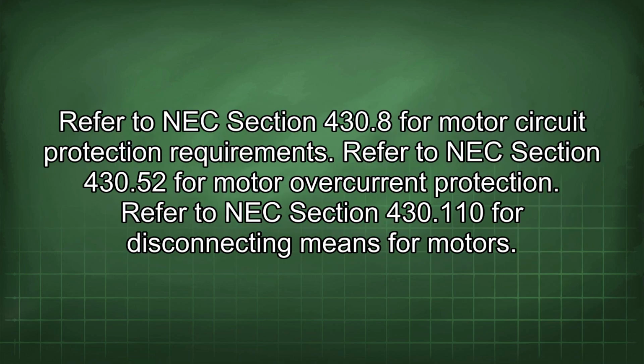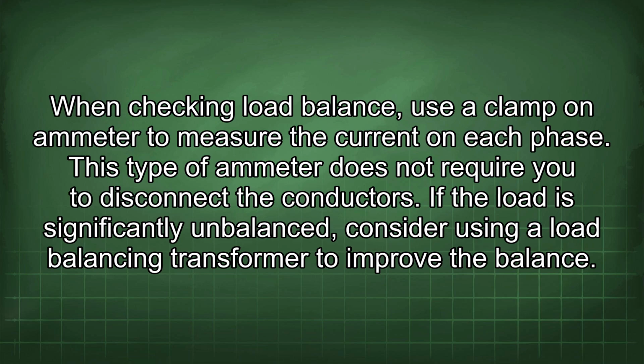Refer to NEC section 430.8 for motor circuit protection requirements. Refer to NEC section 430.52 for motor overcurrent protection. Refer to NEC section 430.110 for disconnecting means for motors. When checking load balance, use a clamp-on ammeter to measure the current on each phase. This type of ammeter does not require you to disconnect the conductors. If the load is significantly imbalanced, consider using a load balancing transformer to improve the balance.